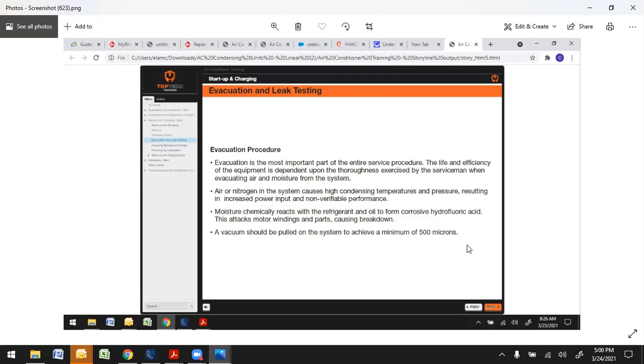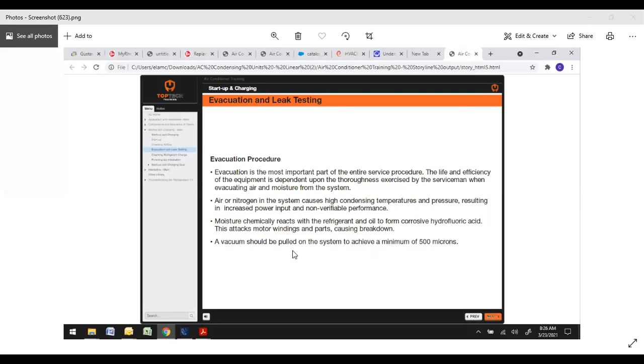So the ideal way to do that would be to get down to about 4,000 microns, do a quick nitrogen purge, then draw it down again to 1,500 microns. Once you reach 1,500, do a quick nitrogen purge, then draw down to 500 microns. Once you get down to 500 microns, let that sit and verify that it does not rise above 500 microns. So that's every service call, every installation. I can't tell you how important that is.